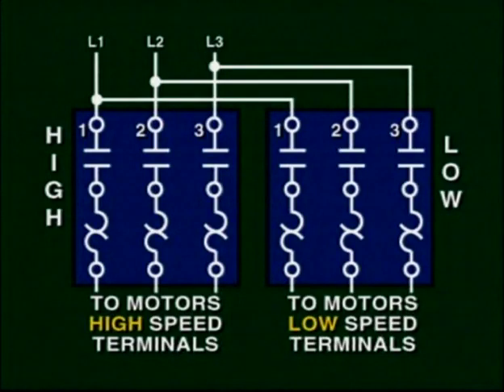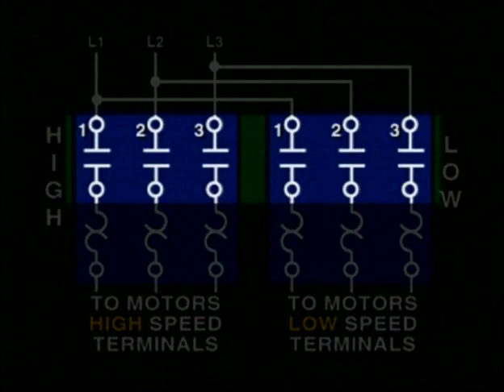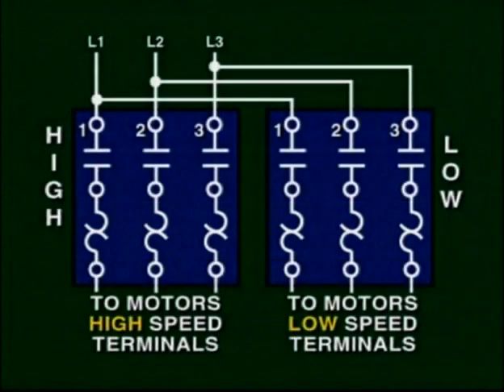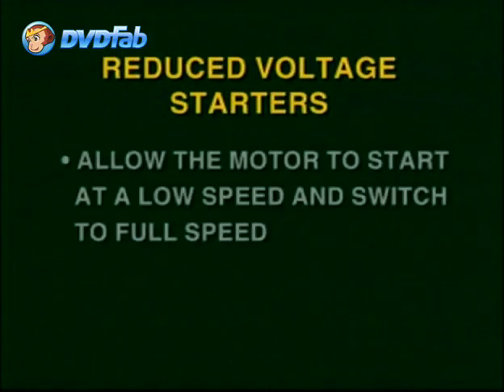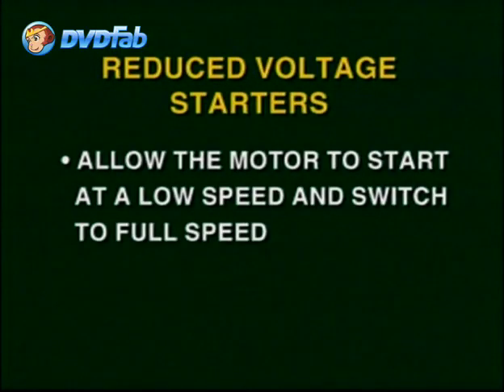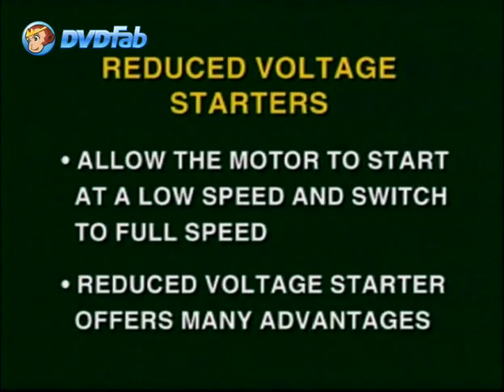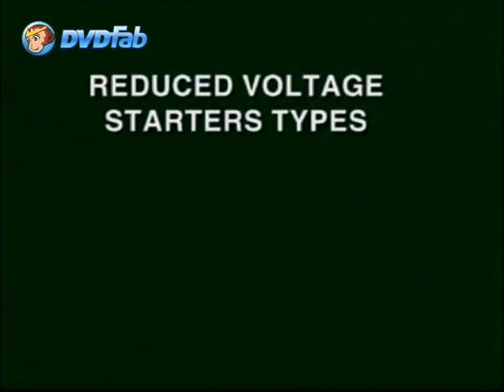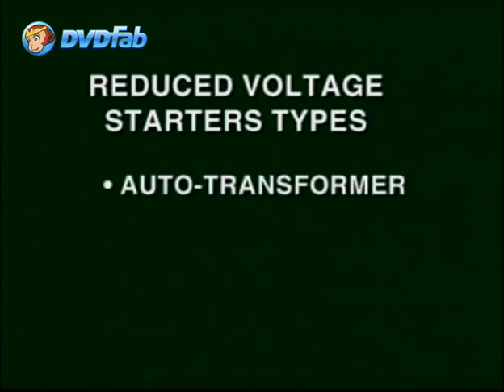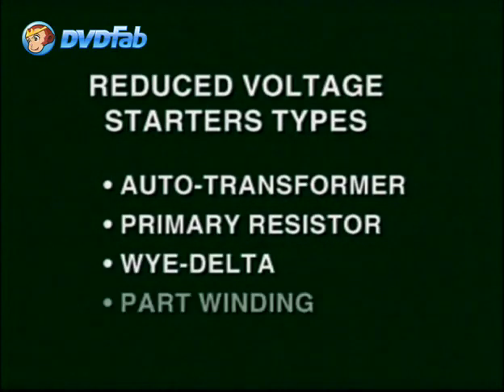The two-speed motor starter, as its name implies, provides two complete starters, that is, with two contactor sides and two overload relay assemblies to control two-speed motors. These speeds are low and high. Reduced voltage starters are available to control and allow a motor to start at a lower speed and then switch it to full speed. There are many advantages in using this acceleration method. There are four basic types or designs of reduced voltage starters. These are the auto-transformer, primary resistor, Y-delta, and part winding, each one providing advantages and disadvantages according to the application.